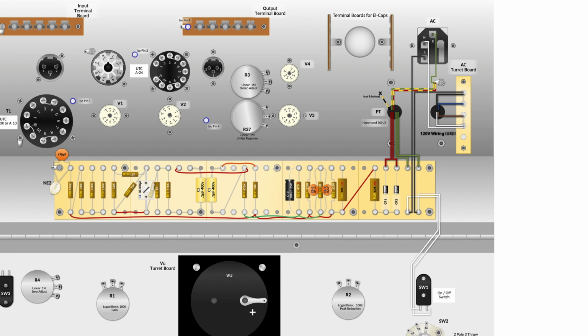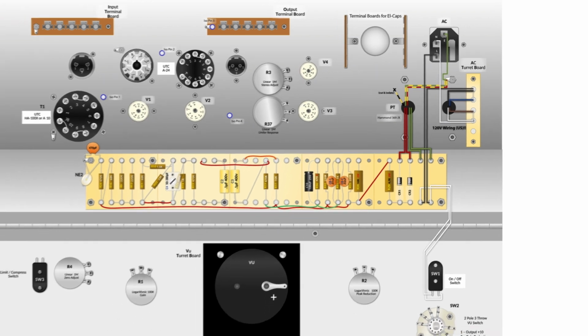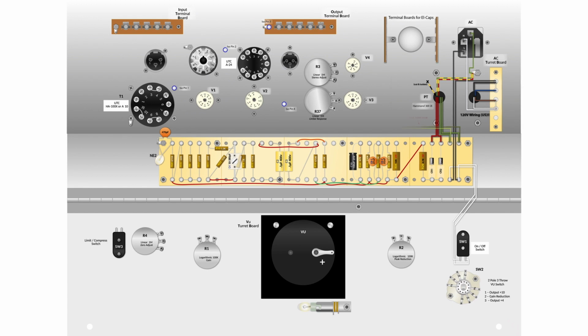All other wires from your power transformer, as an example shown here, the black and yellow wire, need to be cut and isolated with a piece of shrink tube and then stuffed somewhere inside the enclosure where they don't get in your way. As mentioned before, the low voltage line is there to supply the tube heaters.